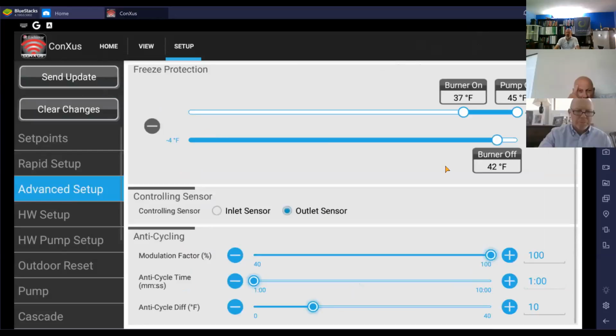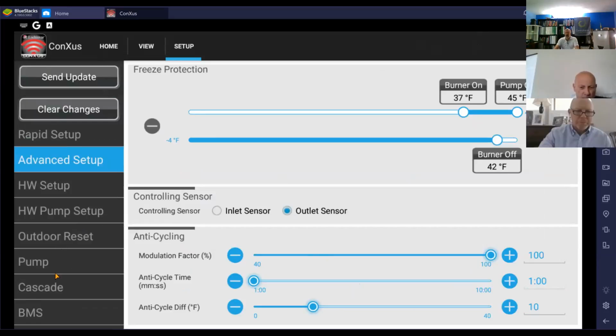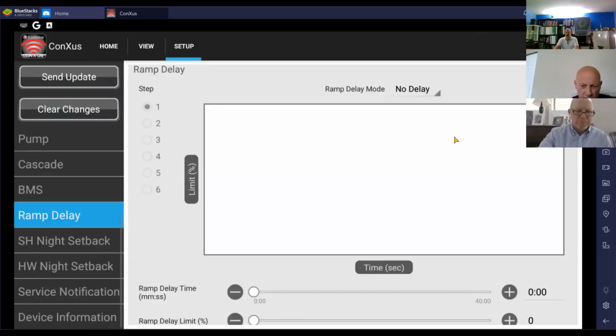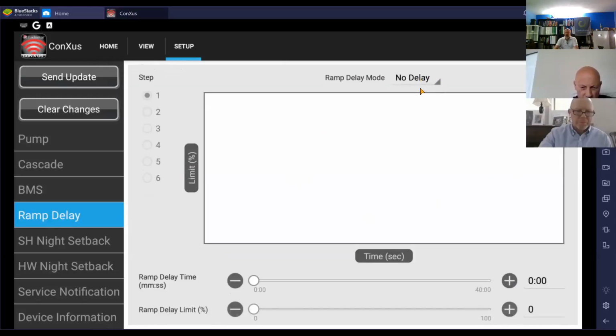Different setup screens that we can get at and what we want to do. If I had a boiler that maybe was cycling more than I wanted it to, I can get right into here and adjust some of the stuff, modulation factor - that's changing the logic within the boiler as to how fast it's going to respond. If I want to change ramp delay, I'm going to do that right here. Now you notice it's not set up in this - this is a member boiler, not a leader. So when we're in the cascade, we actually set all that information up in the lead boiler.